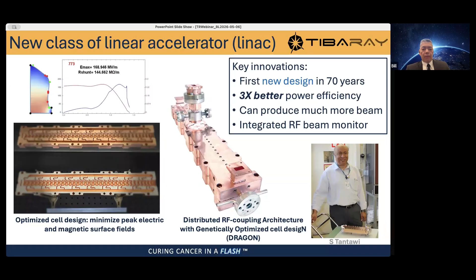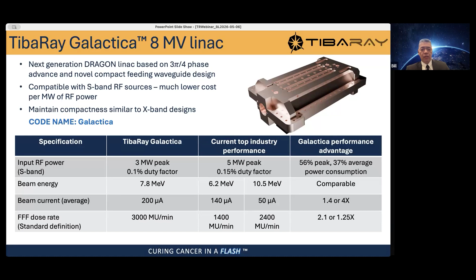This is the first version that is being commercialized now. It's based on that very efficient accelerator design. This is not to produce flash right from the outset, but it is outperforming anything currently in the industry. So what you can see is that this accelerator, if you look at that bottom row, the 3,000 monitor units per minute is the measure to refer to here. That is the rate of radiation that can be produced by this novel accelerator using a very modest amount of input power. And by comparison, the top performing medical linear accelerator in the industry uses more power to produce less beam. And so there's a tremendous advantage of the efficiency of this new design.